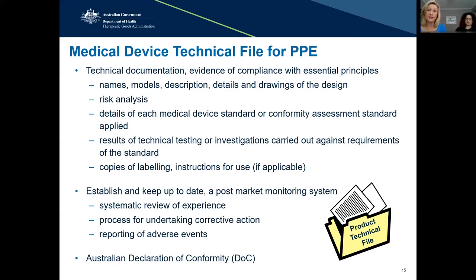A lot of the technical requirements specific to PPE are generally well covered in medical device standards, and there are a number of standards relevant to PPE. Compliance with specific standards isn't mandatory, but it is one of the easiest ways to demonstrate compliance with the essential principles, because it sets out the requirements for technical testing or investigations the manufacturer has to meet.